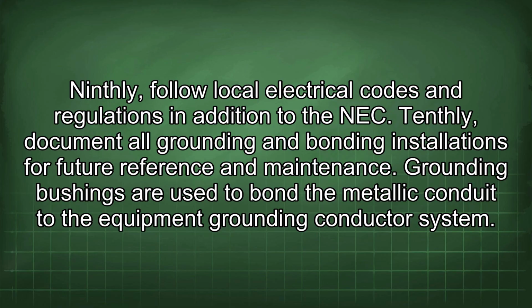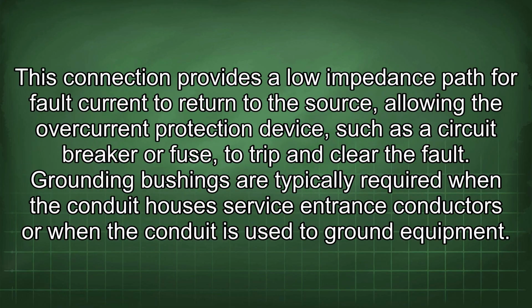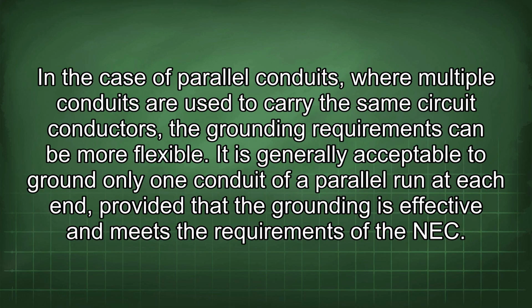Grounding bushings are used to bond the metallic conduit to the equipment grounding conductor system. This connection provides a low impedance path for fault current to return to the source, allowing the overcurrent protection device, such as a circuit breaker or fuse, to trip and clear the fault. Grounding bushings are typically required when the conduit houses service entrance conductors or when the conduit is used to ground equipment. In the case of parallel conduits, where multiple conduits are used to carry the same circuit conductors, the grounding requirements can be more flexible.